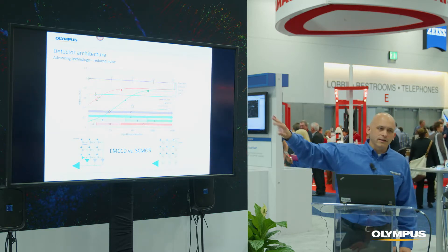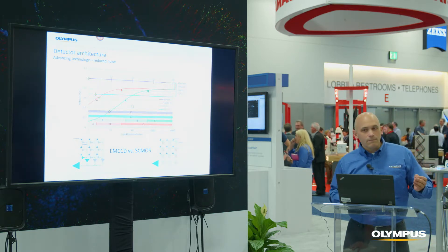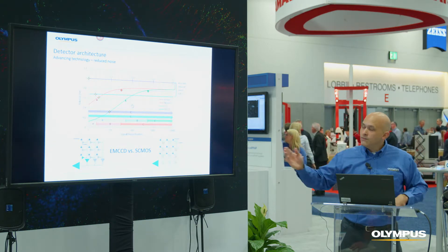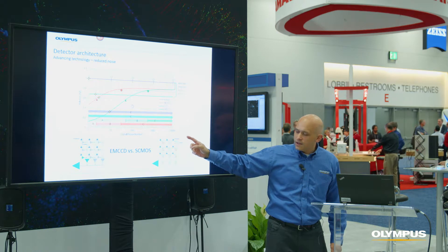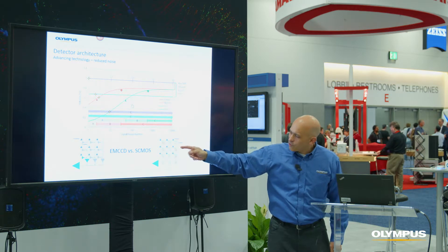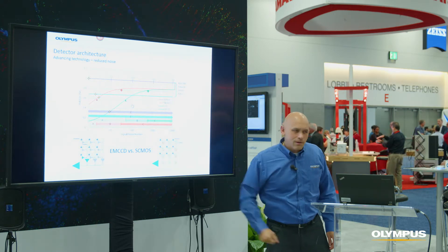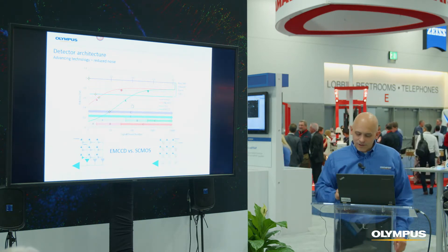Detector architecture is very important as well. The red line shows the sCMOS capability as compared to the green line, the EMCCDs, which have typically been the go-to camera for low intensity imaging. When you don't have a lot of photons, sCMOS is actually a better device, mainly because of the way the cameras work. For a typical EMCCD device, you've got to transfer charge out of the camera, and every time you do this the camera adds noise. Many fewer transfers of charge occur in an sCMOS camera, so you don't get as much added noise. We want to translate all those benefits into resolution, because that's what we really care about.